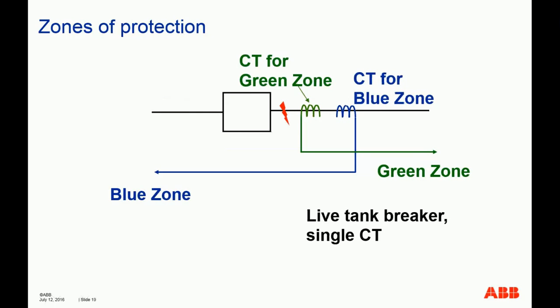So similarly, for the other case, we have this type of situation. The same fault hits here, and you have a CT, and this CT now is not overlapping across the breaker. So your CT is here. As you can see, when the fault is here, in this situation, the protective relay, the differential relay for the green zone, will not operate because it is considered an external fault to it. The blue zone will operate.